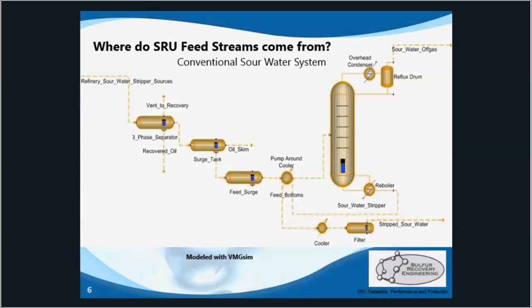All refineries also have a sour water stream, and this is routed to a sour water stripper, which removes H2S and NH3, which is ammonia. Sour water strippers include a regenerator or stripper, which removes H2S and NH3 from solution in the form of acid gas. This acid gas stream contains approximately equal parts of H2S, NH3, and H2O, as well as other trace contaminants, which we hope to be minimized.